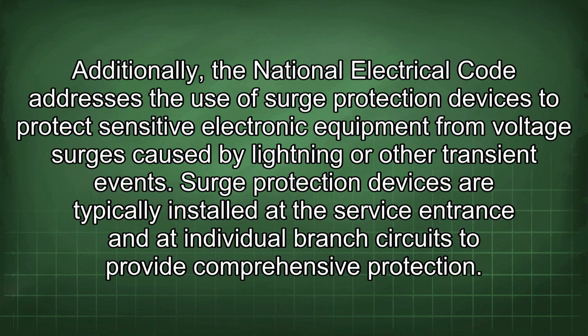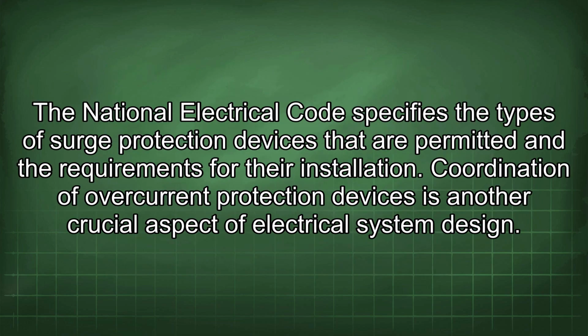Additionally, the National Electrical Code addresses the use of surge protection devices to protect sensitive electronic equipment from voltage surges caused by lightning or other transient events. Surge protection devices are typically installed at the service entrance and at individual branch circuits to provide comprehensive protection. The National Electrical Code specifies the types of surge protection devices that are permitted and the requirements for their installation.